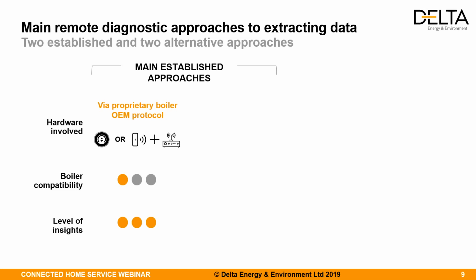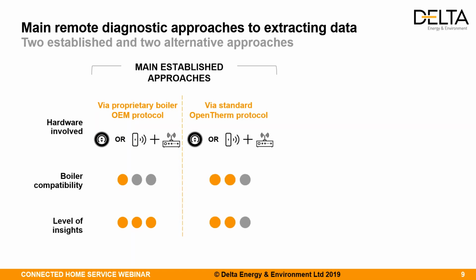Of the two established approaches, one is using proprietary boiler OEM protocols. This would be each of the large boiler manufacturers having their own protocol, only working with their own boiler. So this offers low boiler compatibility, really only with that specific brand. But the level of insight can be very high, and some of the larger boiler manufacturers will be getting hundreds of data points, well over 100, from the boiler.